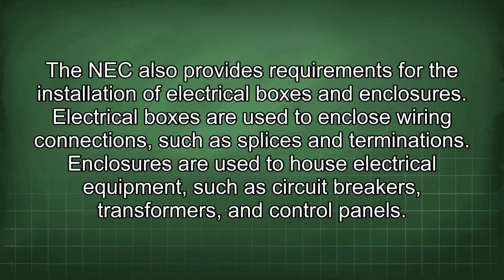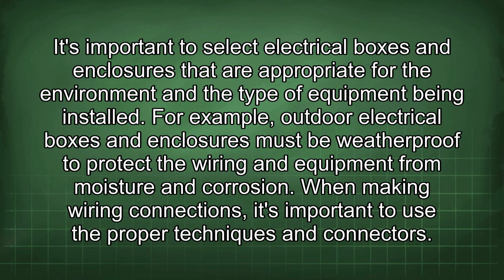The NEC also provides requirements for the installation of electrical boxes and enclosures. Electrical boxes are used to enclose wiring connections such as splices and terminations. Enclosures are used to house electrical equipment such as circuit breakers, transformers, and control panels. It's important to select electrical boxes and enclosures that are appropriate for the environment and the type of equipment being installed. For example, outdoor electrical boxes and enclosures must be weatherproof to protect the wiring and equipment from moisture and corrosion.